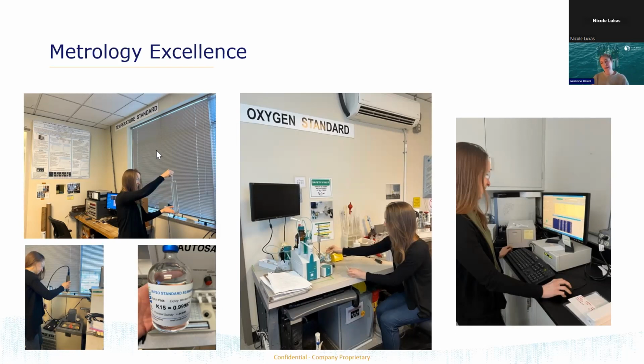We will put them into our oxygen baths, which step through a variety of different temperatures and different oxygen saturations. And as they hit those different points, we actually grab a water sample. We fix the amount of oxygen in that water sample, and then we titrate it out, so that we'll compare that truth of how much oxygen was in the water to what the sensor was reading. And then we use those stable sensors as our references.